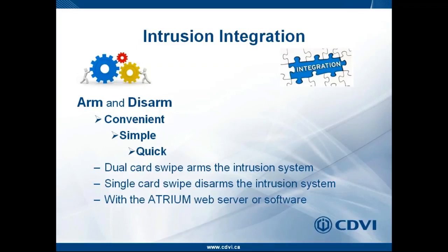So we will override the access rights of the users that do not have disarming access if the alarm system is still armed. So you must have disarming rights to be able to gain access to that door. Once the system is disarmed, then the employees' access levels and all the access levels will begin functioning normally.